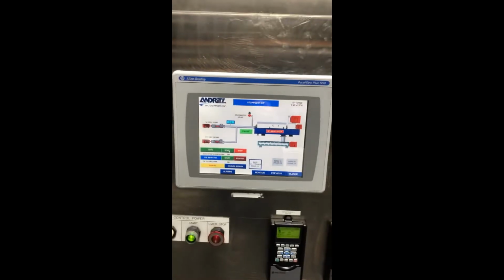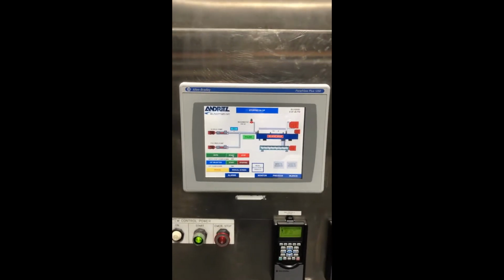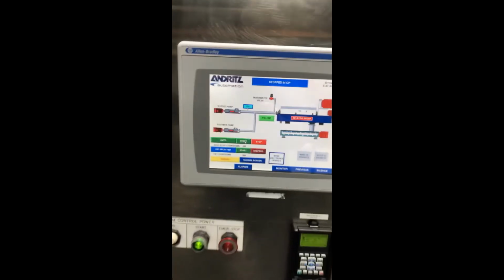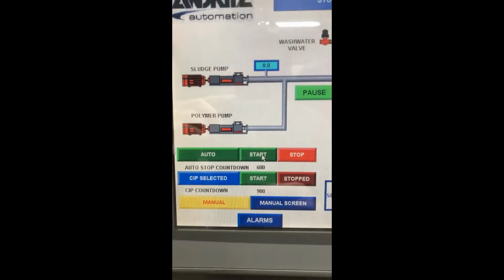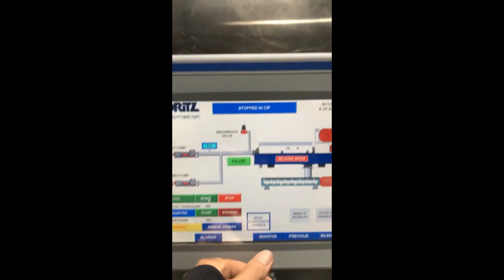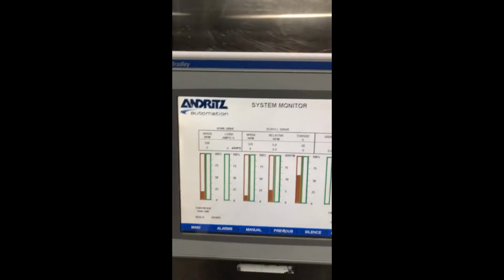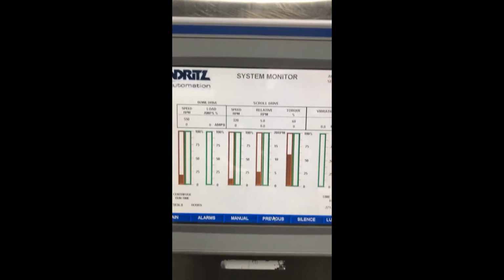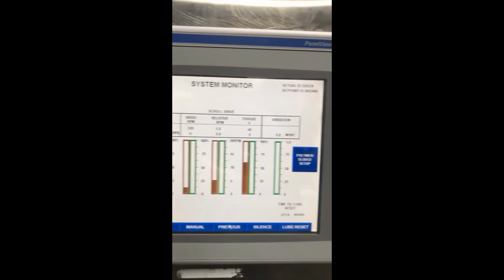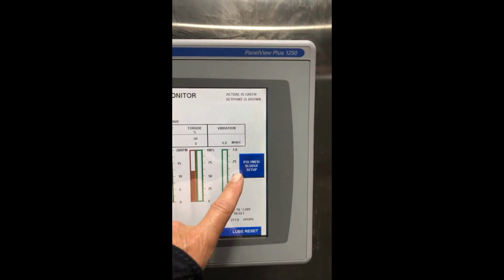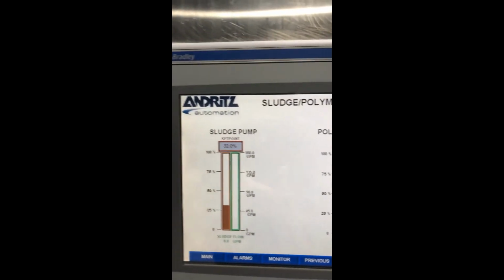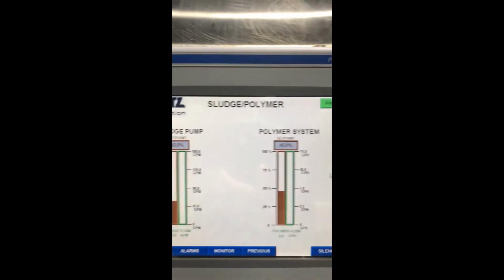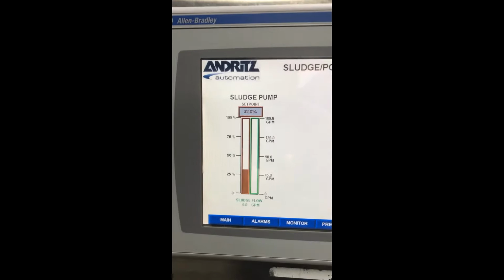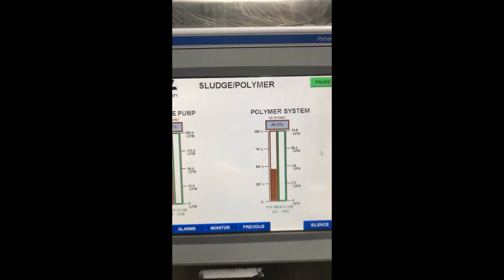This is our local HMI for controlling this machine. Here the operators are able to start, stop. They're able to monitor all the variables that are real time. They're able to go over to the polymer set points for the sludge and the polymer, the flow for the sludge, and how much they feed to the machine.